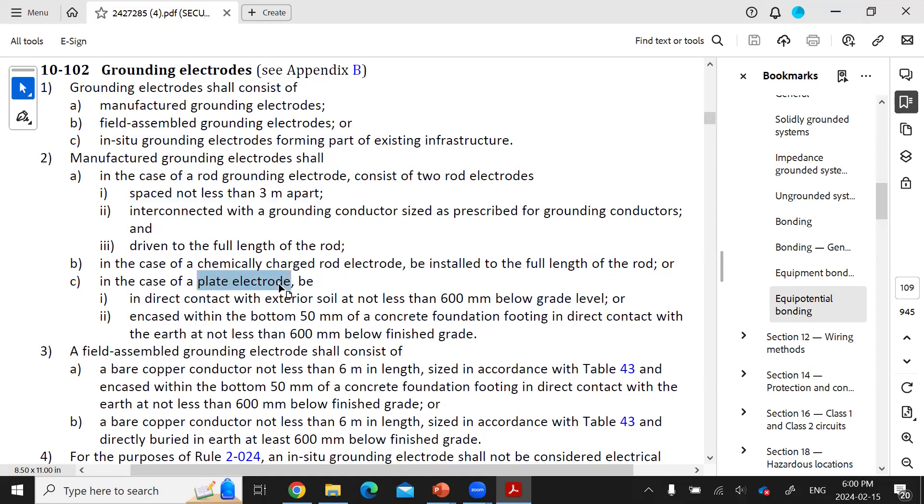The electrodes must have an exterior surface area of at least 0.2 meters squared, and all of that is in contact with soil. They must be buried at least 600 millimeters below surface grade. They must be encased within the bottom of a 50 millimeter concrete foundation footing that is in direct contact with the earth, with the concrete having an exterior surface of at least 0.4 meters squared and the burial depth not less than 600 millimeters below finished grade.